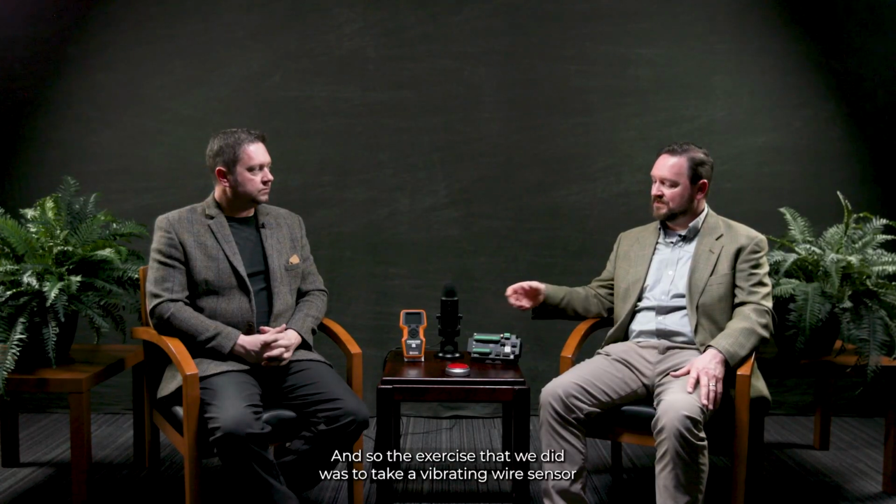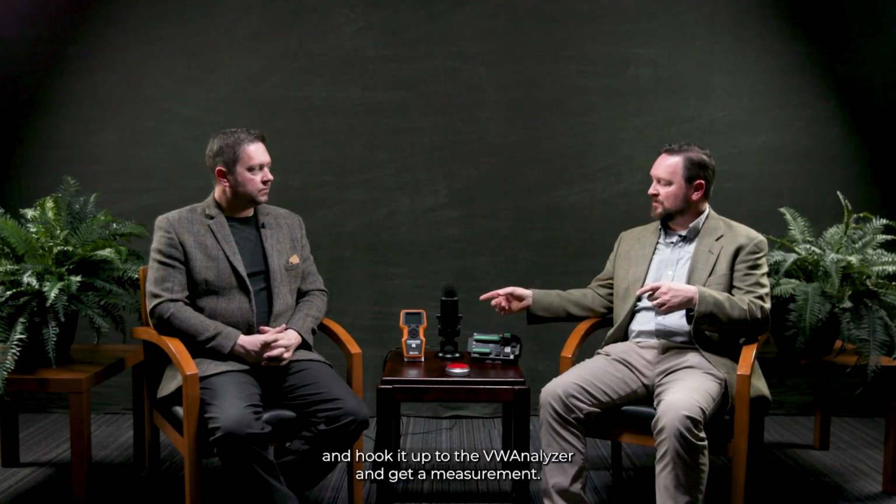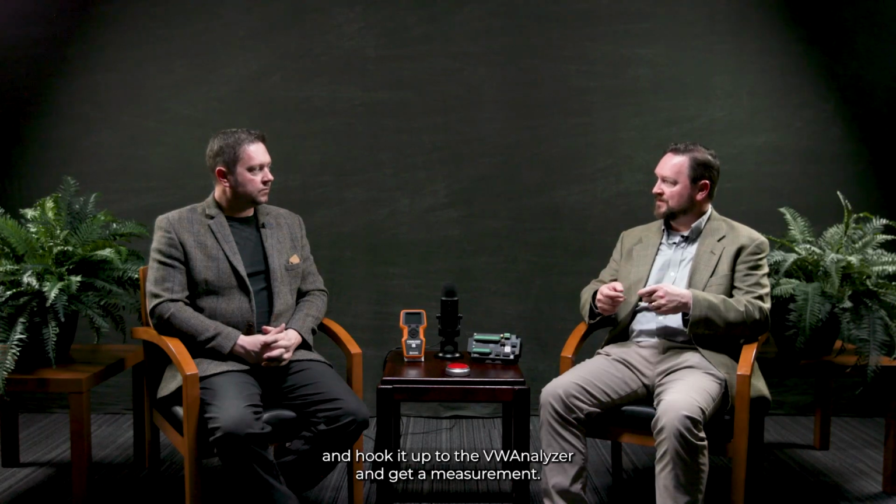This is what led to the whole conversation when I was in this training. One of the clients asked, why does it matter, the sensor diagnostics? And the answer that I gave him was that vibrating wire sensors have such a long life, they can last for decades, that it's really important to understand the quality of the sensor after it's been in the field for such a long time. And so the exercise that we did was to take a vibrating wire sensor and hook it up to the VW Analyzer and get a measurement.